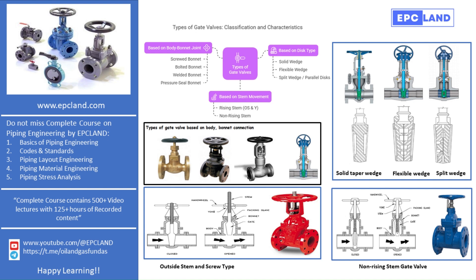The non-rising stem, or inside screw type, has the stem not moving up or down. Instead, the disc moves along the threads of the stem inside the valve. The stem threads are in direct contact with the flow medium. That's why this type is suitable for places where vertical space is limited and the fluid does not damage the stem material.